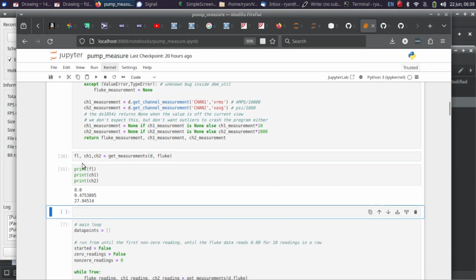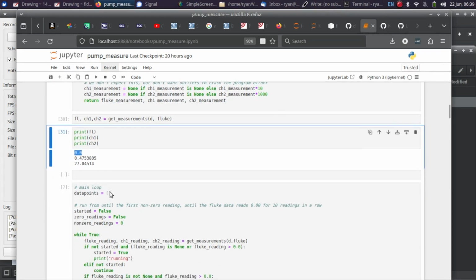I have just a little test here to read samples from all three. So we can see the Fluke reading on the AC amp clamp is 0.0. The current clamp on the scope is reading 0.475, and this is part of the reason I wanted 2 amp clamped inputs. I don't know if it just doesn't zero properly or if it is not calibrated in a more skewed manner, but I wanted to have the precision of this amp clamp and the accuracy of the Fluke one. And then the pressure transducer is currently reading 27 psi.